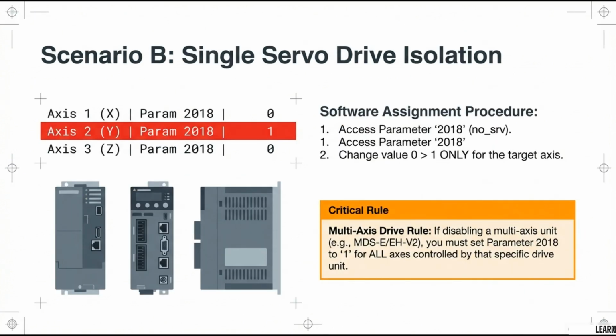Scenario B is single servo drive isolation. The software assignment procedure is to access parameter 2018 and change the value from 0 to 1 only for the target axis. For multi-axis drive units, set parameter 2018 to 1 for all axes controlled by that unit.